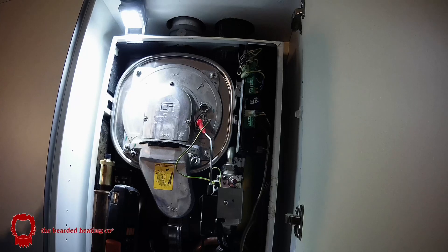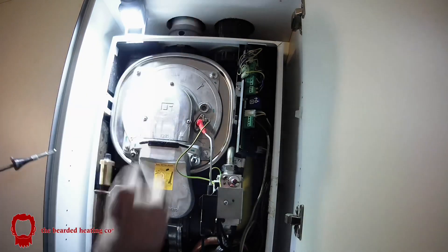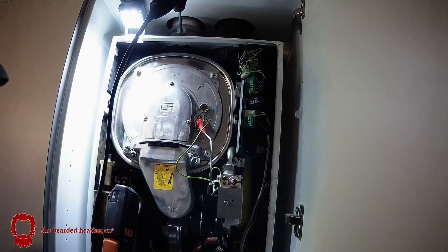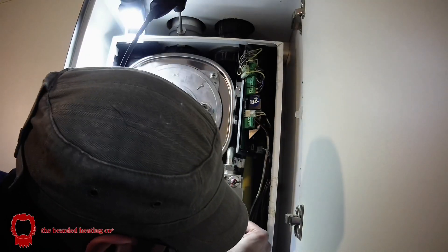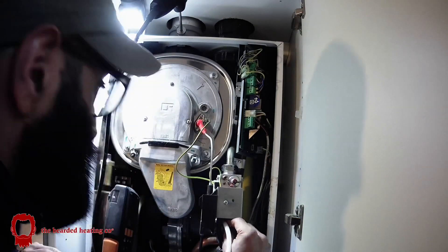Once that's done I always carry out my FGA test. On a Remeha Avanta on high fire and low fire, the CO2 should be around 8.8, and obviously parts per million less than 200. And I always test my inlet working gas pressure as well to ensure there is sufficient gas at the boiler.